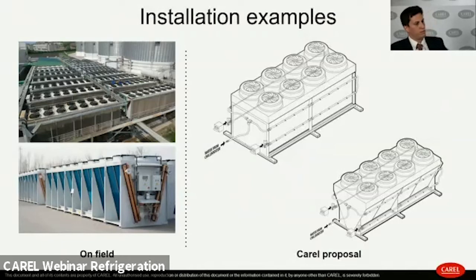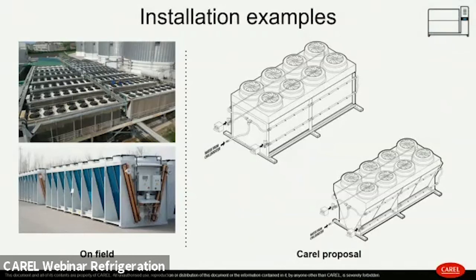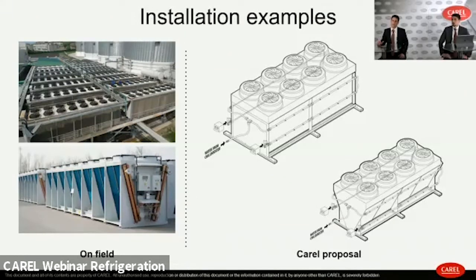Okay, we have seen some details of the product. We can now see some installation examples, so how the system can be installed on a heat exchanger. Here in the picture, we have two examples of really common heat exchanger geometry, the vertical one on the top and the V shape on the bottom. The suggested installation layout is all around the surfaces in order to cover the frontal area of the heat exchanger. And we suggest placing the nozzles spraying out towards the inlet airflow and placing the manifold 30 centimeters far from the heat exchanger. In this way, we can obtain the best distribution in terms of water nebulization.